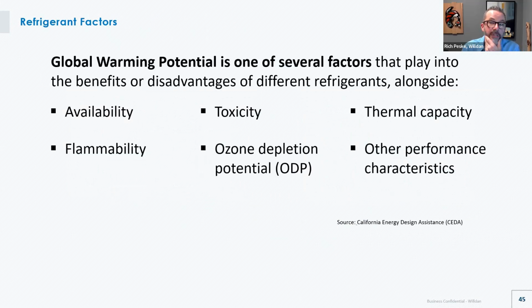So I do need to point out, I like to mention this: global warming potential is one of many factors, right? And choosing your refrigerant can be affected by other things, like, is it available in the system I'm looking at? How toxic is that refrigerant? Is it flammable? Ozone depletion? All of these things. So I would never say that you should choose something solely on GWP, but I would encourage you to consider it strongly with all the other factors.